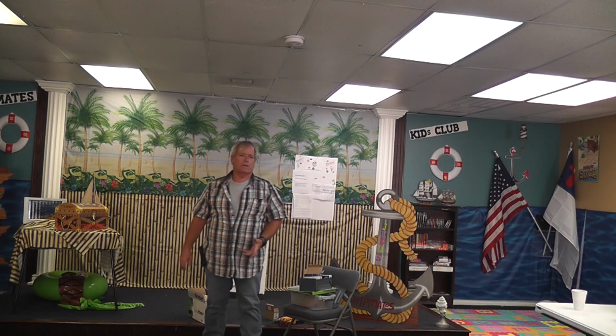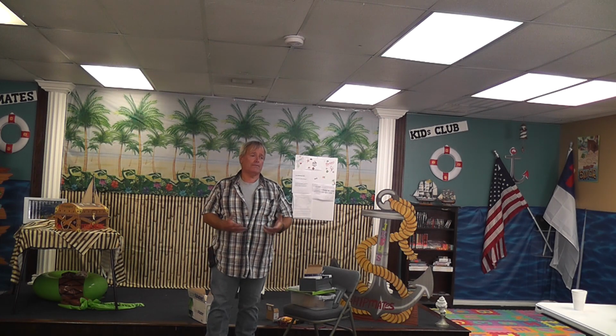This is a 75. A lot bigger. There's multi-tap on them, 120, for a very specific reason. When you go up to the machine, I don't think there's 110 on there, but you could have a 110 volt circuit inbound. You could have a 208 voltage circuit inbound. You could have a 230 volt inbound. You could have a 460 volt inbound. And you have to get down to 24. You have to have the right one.